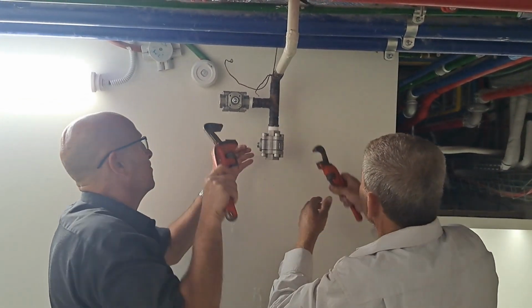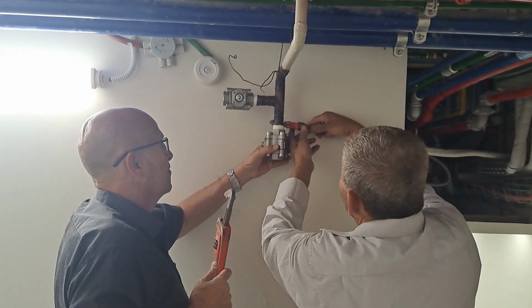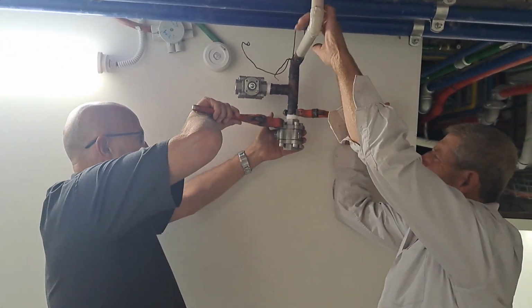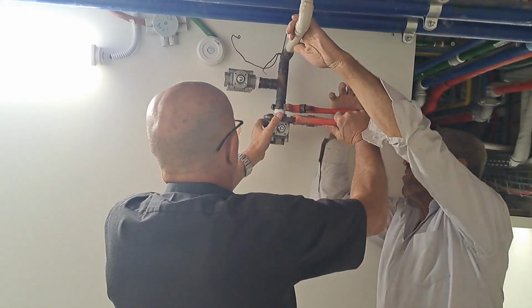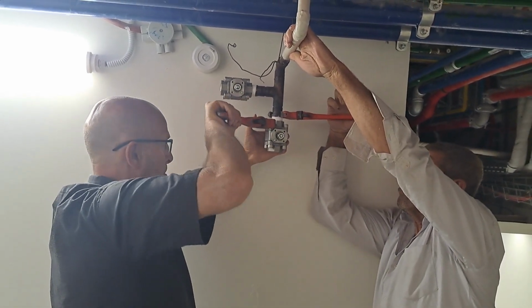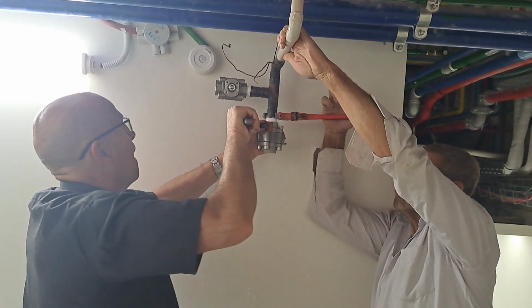The connection to the magnet is via a stainless steel bellows. Had the building vibration been a problem, the magnet could have been connected via a nipple between fills using flexible silicone tubing.